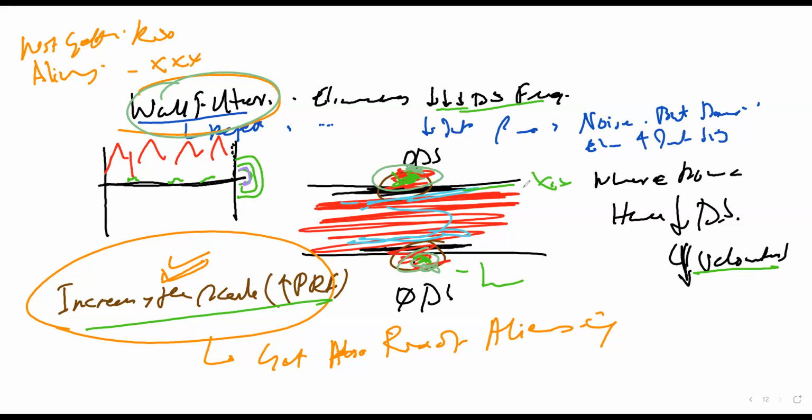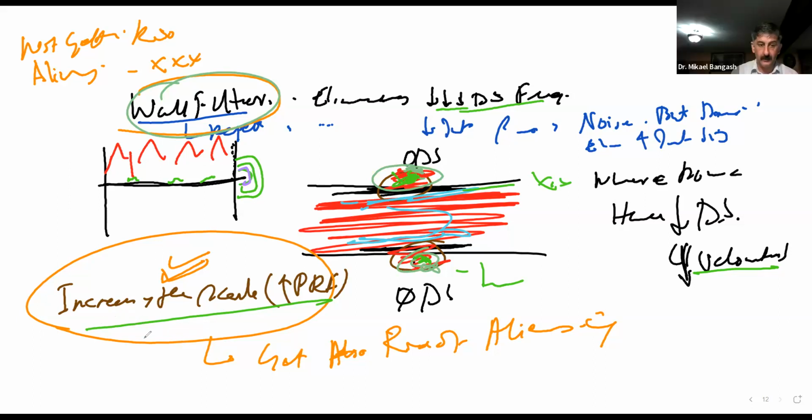Yeah. That is mainly because increasing the scale causes reduced sensitivity. Reduced sensitivity means that we will not be able to register the low Doppler shift frequencies due to low velocities, which in this case produced this artifact that we call ghosting.